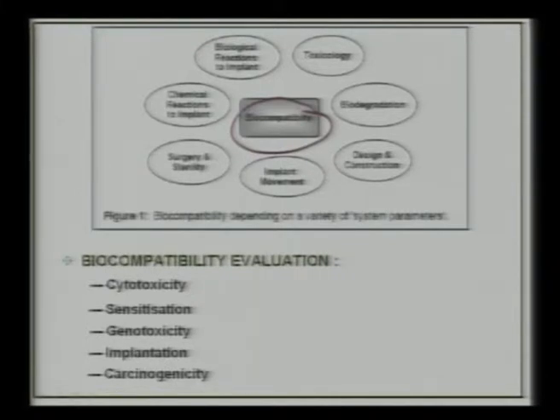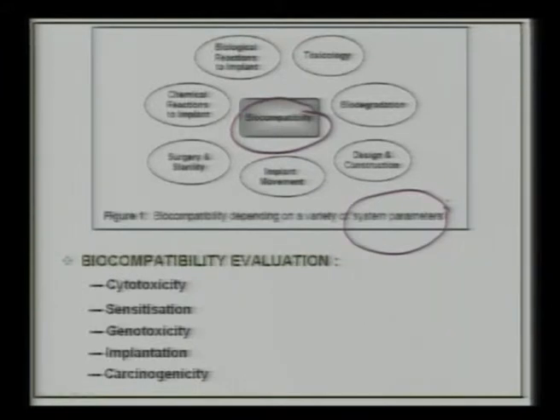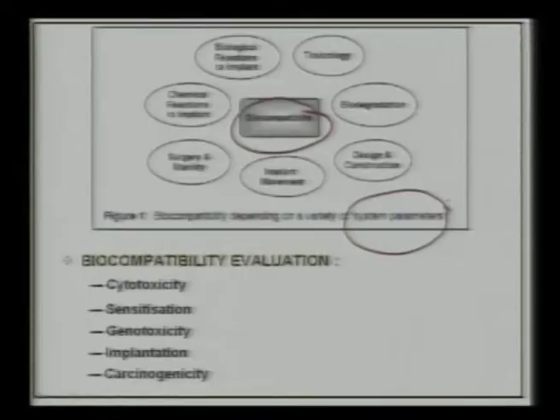It is important to know how biocompatibility can be assessed. First, biocompatibility is a system property — it means if your material is biocompatible for a particular application, that does not necessarily mean the same material is biocompatible for another application. For example, a material biocompatible for knee replacement may not be biocompatible for heart valve applications, because the requirement is application-specific.